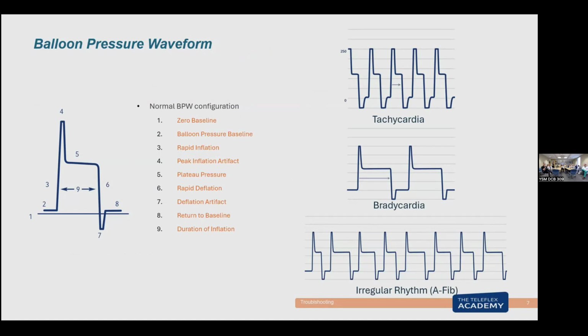So, the balloon pressure waveform. I'm just going to flip up here and post this. We have a zero line. This is the helium zero line on ours. It comes up and fills the bellows, so we've got the helium ready to go out to the balloon. Now the pump pushes the helium out to the balloon. We go straight out. There is a transducer inside the pump that monitors this helium going in and out. As it goes past that transducer, we get the fling artifact, kind of like when we do a square wave test on an arterial line. Then it settles down and the balloon starts to get fully inflated.